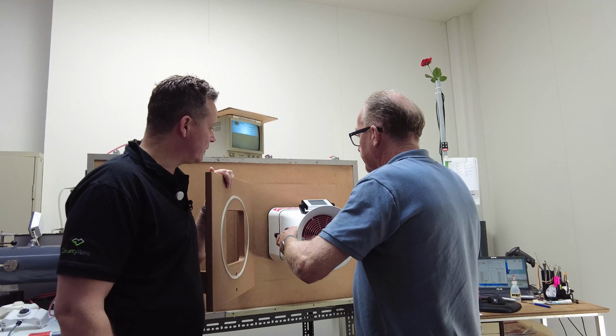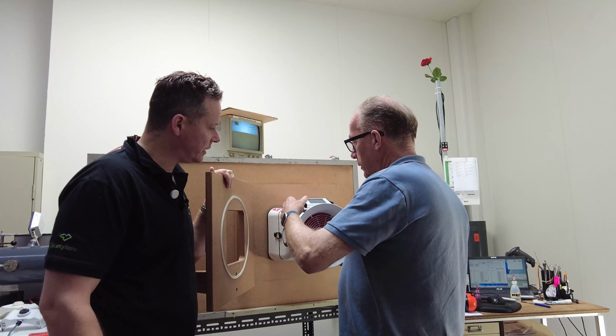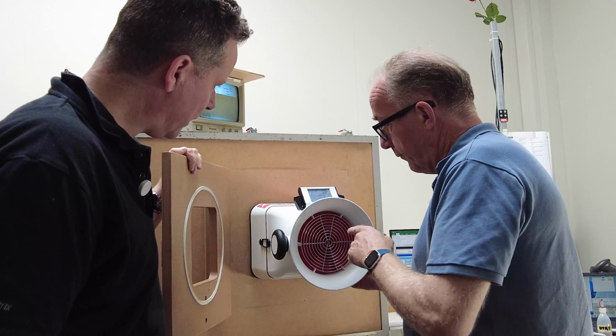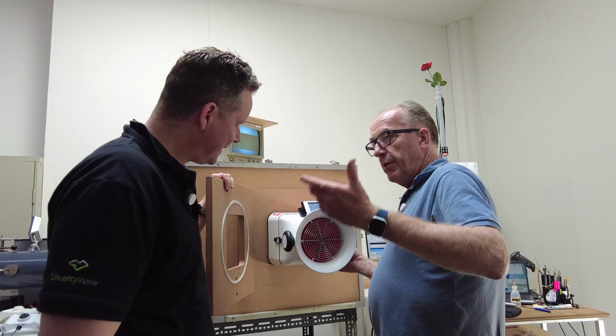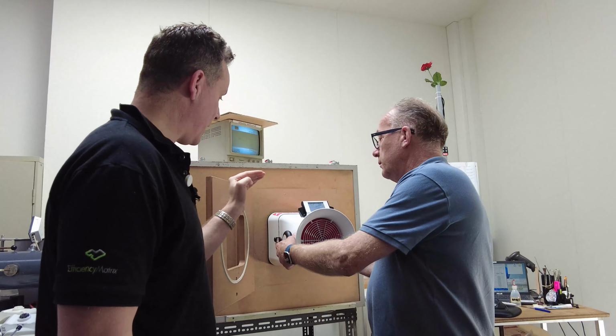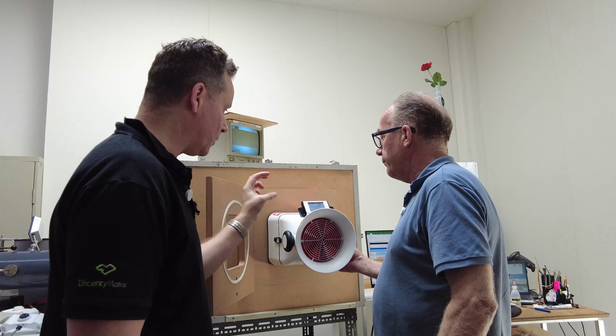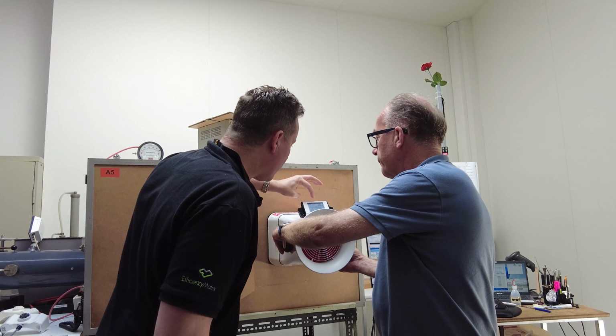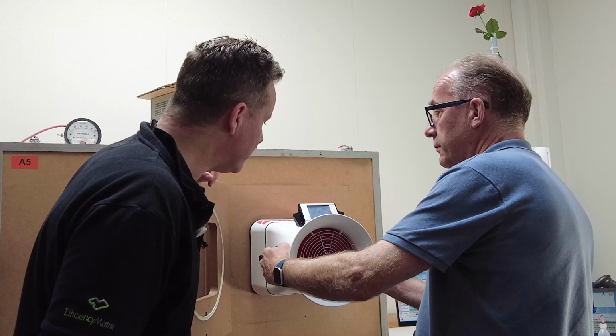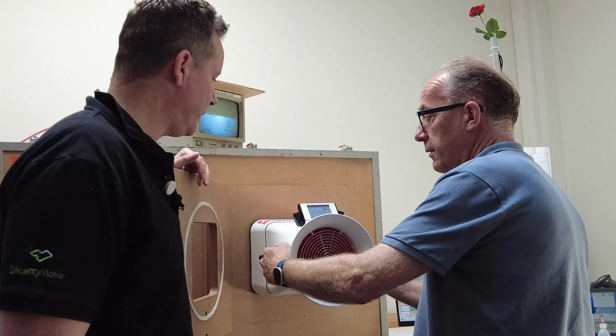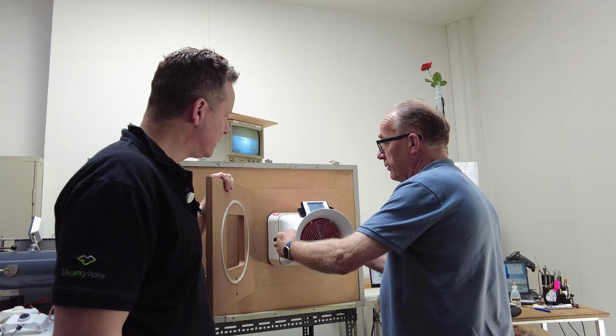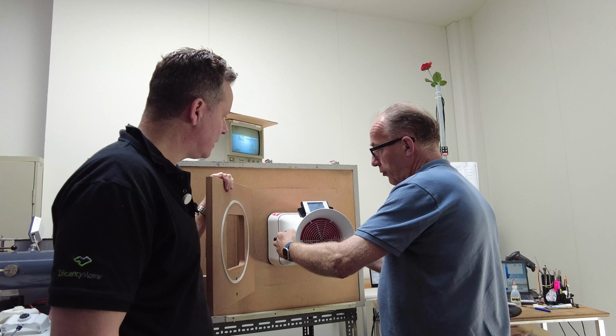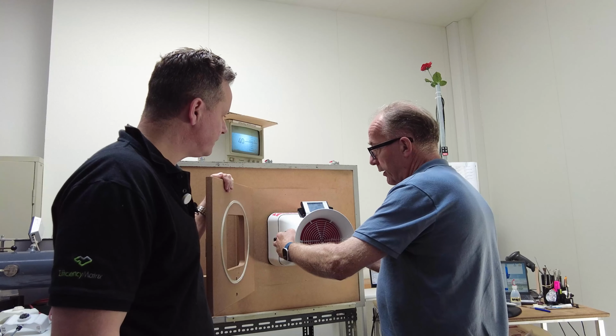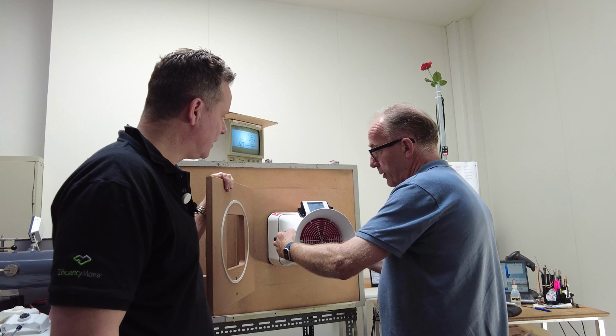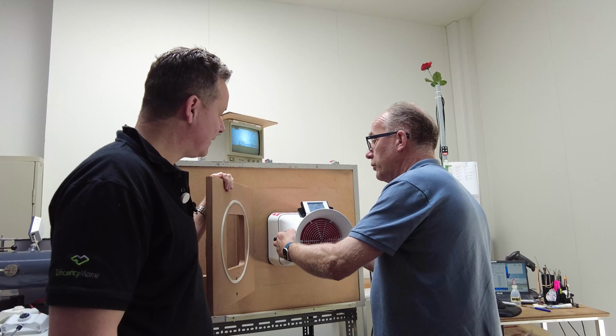So you're putting it over the top of this airflow here from the calibration rig. And we now have a flow where the fan is already rotating based on the passive measurement. So you have not activated the onboard fan yet to equalize the pressure inside. No. And you've got a pressure in here, 7 Pa, 6 Pa. And then you press the button, and you're going to turn that to 0. It is sort of looking for the 0 point. There it's speeding up and it's already getting close to 0. Wow. Now it needs to take a few measurements of the rotation and it gives you 80 cubic meters per hour.